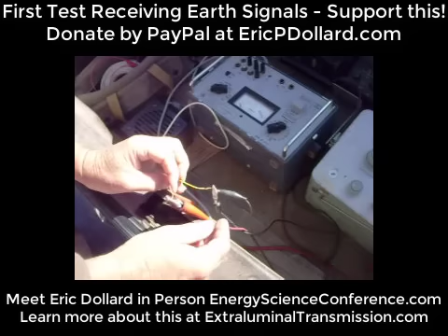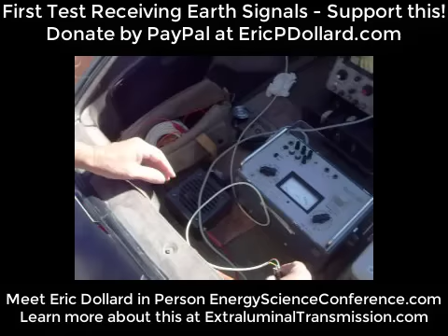So now that we're grounded, we'll go back and take the measurements and see what we pick up. Okay, so right now we have our Earth connection here with our ground system, and then at the other end of the line it's grounded. So what we have is kind of a loop going over ground and then back through the underground.